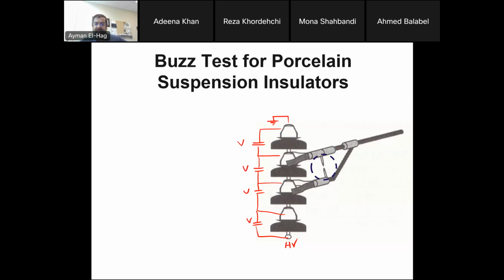So you bring this detector, we call it the buzz. We'll know why it is called the buzz. Basically, you connect it between the cap and the cap of the other insulator. You are connected across the voltage that is developed across the ceramic insulator. So if this insulator is holding that voltage, you'll have a potential difference V between this point and that point. There is a voltage V, okay? And this potential difference will be between these 2 points. So we adjust the distance between 2 sharp points so that when we have this V, an arc will happen here. When you have an arc, you hear a buzz sound. If you hear a buzz sound, it means that this is a healthy insulator.